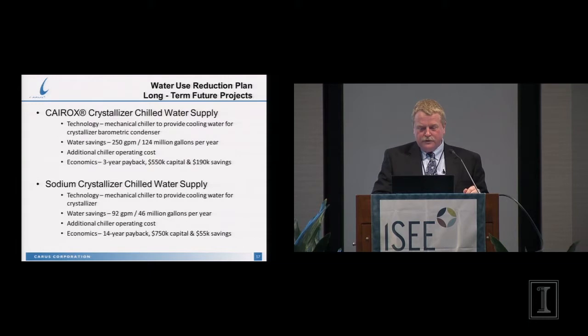So some of the future projects that we're looking at are that crystallizer cooling loop for the barometric condenser. Temperature of that water is critical. We need 55 to 60 degree water for the equipment to perform properly. If the water gets warmer, we don't get as much vacuum, and then it affects our finished products.